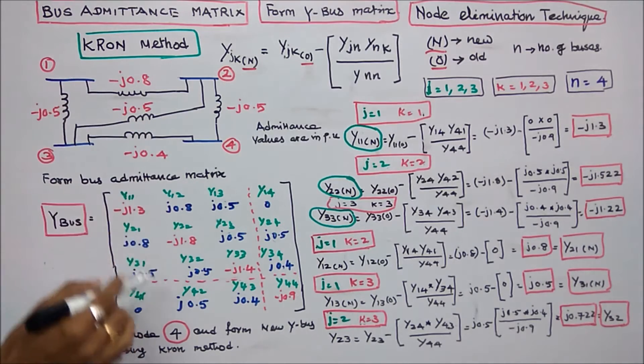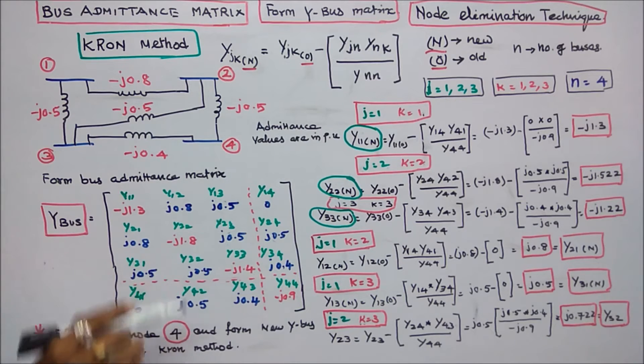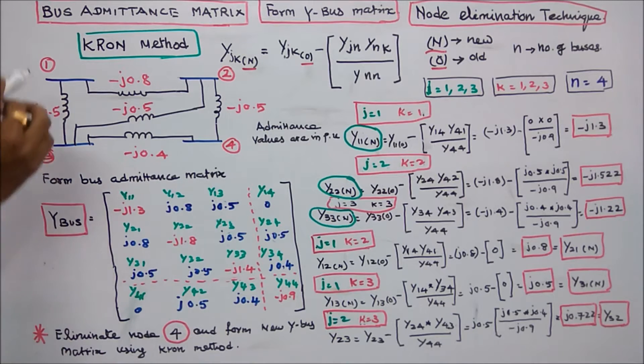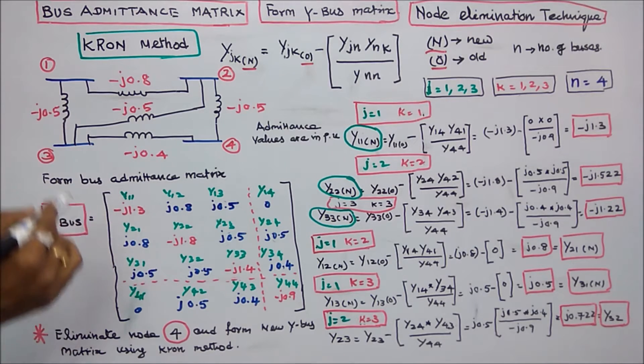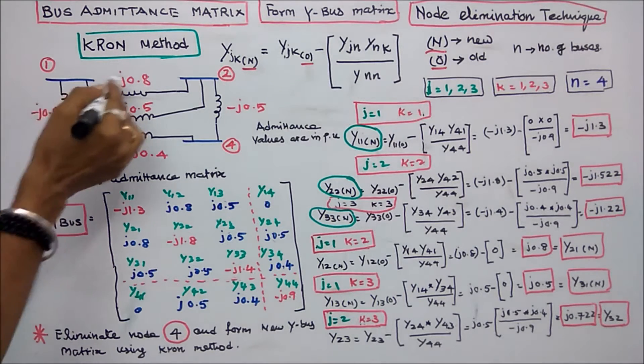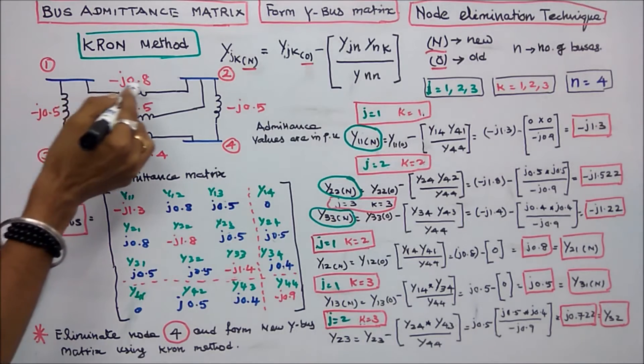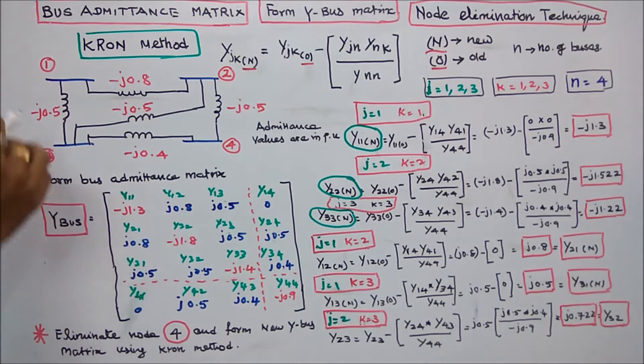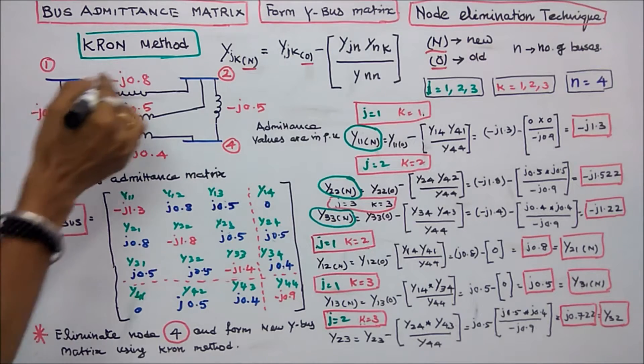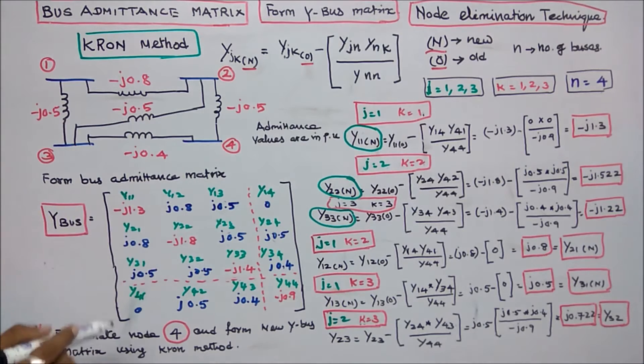The first step is to find the diagonal elements. Y11 is calculated by adding the admittances of the 2 lines connected to bus 1: minus j0.5 plus minus j0.8, giving minus j1.3.